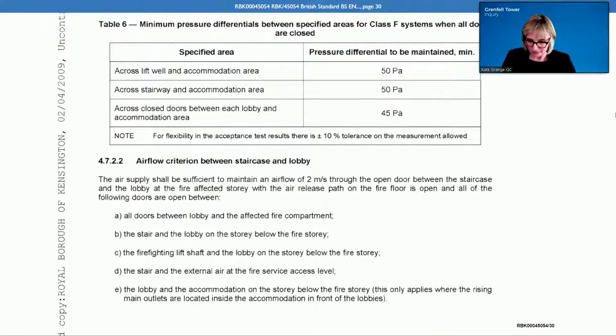So did you consider whether the existing builders' work ducts had a minimum of 60 minutes fire resistance for each side separately? Did you ever actually consider that? Well, it's marked up on the plan, so the expectation is that's the intention. When they actually look at the system, they would need to do a survey of it and decide if there are any problems with the shaft. Any holes need to be filled up with fire-resisting material, etc. But we take the plan as an intent to make the shaft fire-resisting. It's got a red or green line round it with a note that mentions it's fire-resisting.